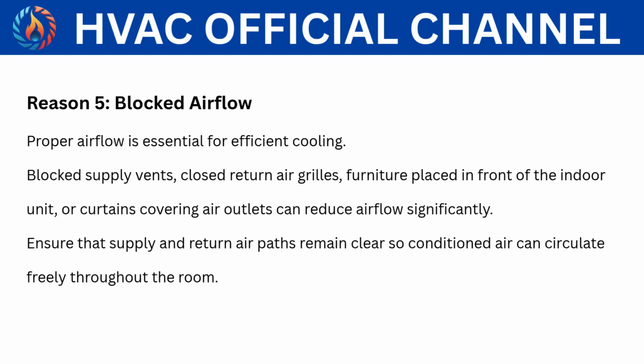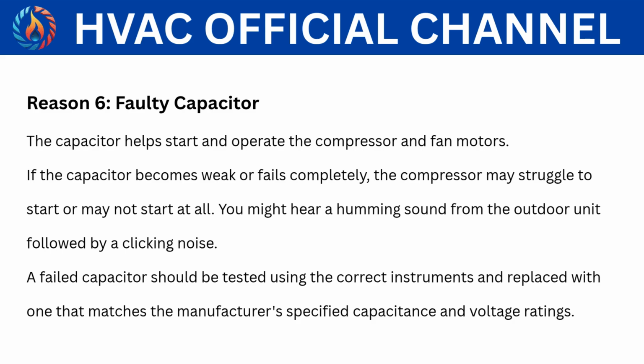Reason 5. Blocked airflow. Proper airflow is essential for efficient cooling. Blocked supply vents, closed return air grills, furniture placed in front of the indoor unit, or curtains covering air outlets can reduce airflow significantly. Ensure that supply and return air paths remain clear so conditioned air can circulate freely throughout the room.